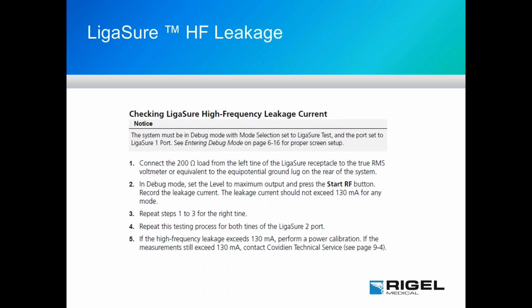Testing LigaSure is going to be much the same, except we're kind of doing a bipolar test. Notice that they have specified 130 milliamps is the maximum amount of leakage current that they want to see on the LigaSure port. So while the 60601-2-2 specification still talks about 150, as a manufacturer, they have chosen to specify something less, 130 milliamps in this case. They never could specify anything more than 150, or they'd be in violation of the standard for ESU generators.